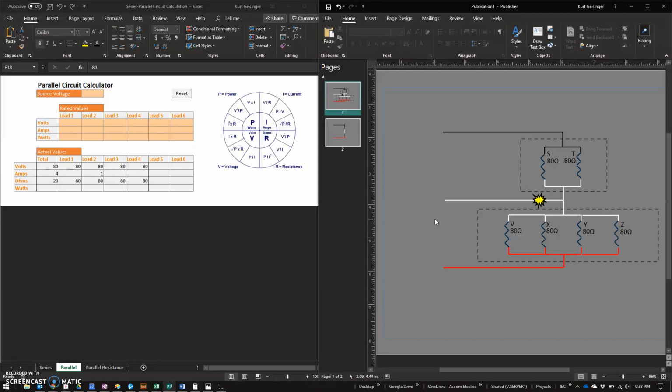This is a very difficult section, and quite frankly, upon reviewing this, I'm going to pull that from your required assignments. I do want you guys to look at this, think about it, and at least understand the brief idea. So if you ever hear a service call where half the lights are really bright, half of them are burned out, some are not working, usually it's a bad neutral, and this is why. Okay, so understand that much.